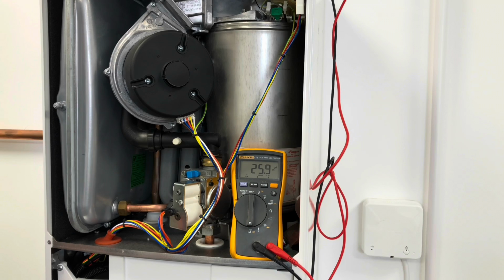27, 26. So again, if somebody set the minimum setting wrong on the boiler, we might lose the ability to record that microamperage through the flame, which could then lead to a potential ionisation fault. So it's important that we test in max and min to make sure that we get what we should receive at the board. So it's important to note as well that not all manufacturers will have the same readings. Very rarely does an instruction manual give you the readings of what you should be receiving in either microamps or voltage DC.